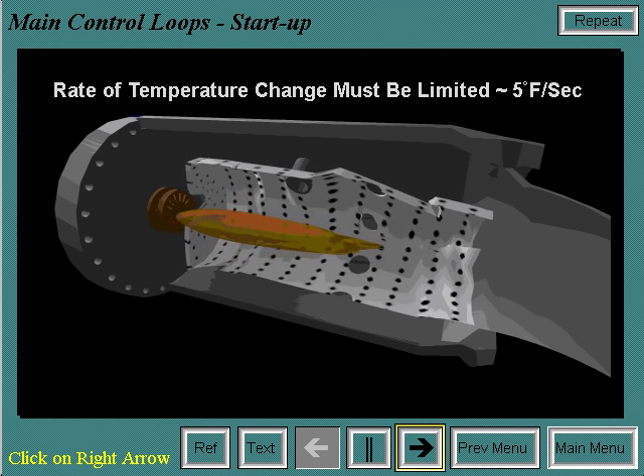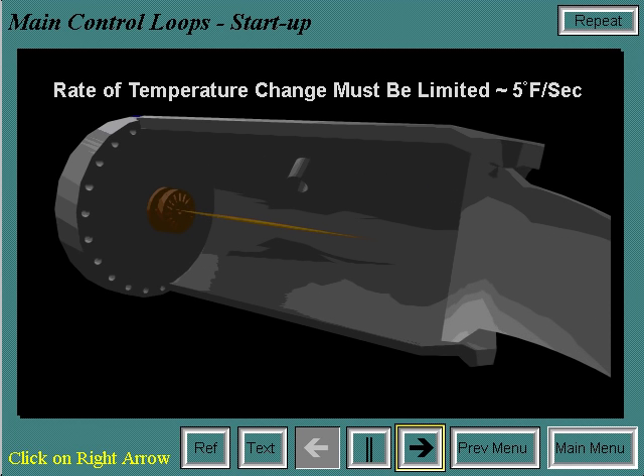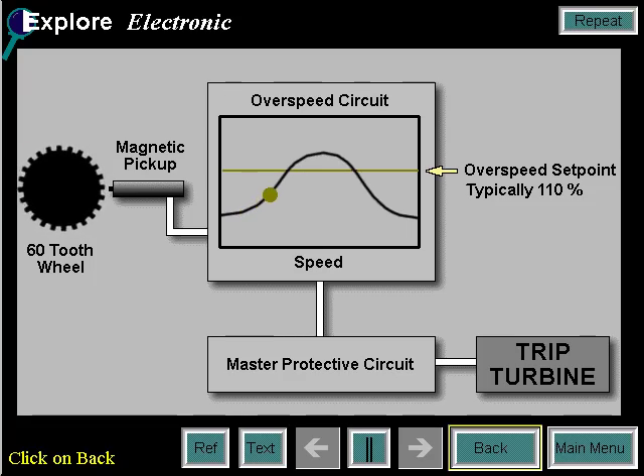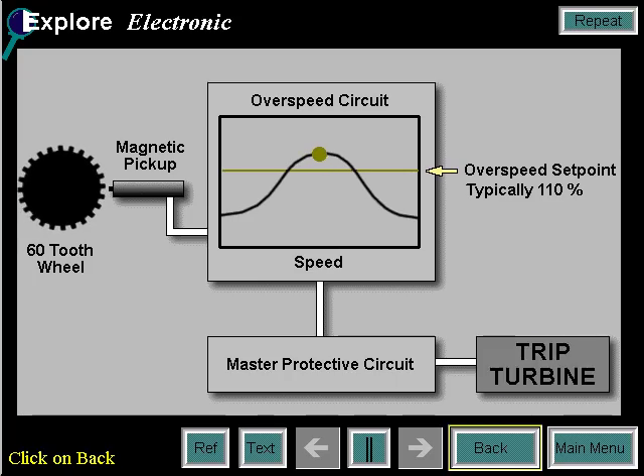High fluctuations in temperature can reduce the life of internal hardware. Different materials heat at different rates, so the rate of temperature change must be limited at approximately 5 degrees per second. The electronic overspeed protection function compares the turbine speed signal derived from magnetic pickup sensors to an overspeed set point. When the turbine speed signal exceeds the set point, the overspeed trip signal is transmitted to the master protective circuit to shut down the turbine.